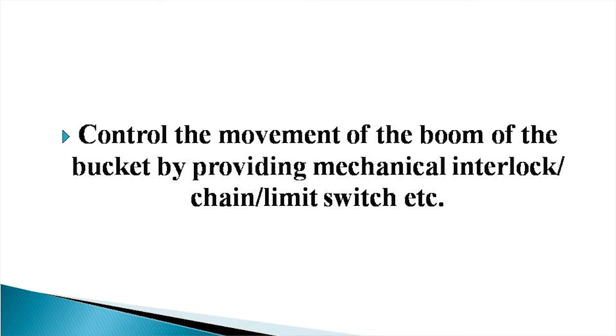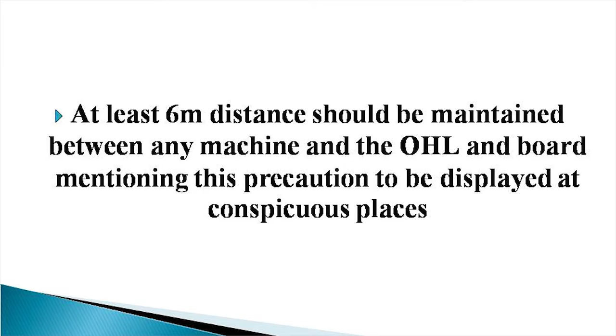Then a proximity warning device should be provided on the machine to warn the operator that he is nearing the conductor or nearing the pole. Warning notices should be posted near all overhead lines for cautioning the operator to keep away from any overhead line. Then at least a 6-meter distance should be maintained between any machine and the overhead line, and a caution board, warning board mentioning this precaution should be displayed at conspicuous places. And while working near any overhead line, all the persons must use insulated rubber gloves.